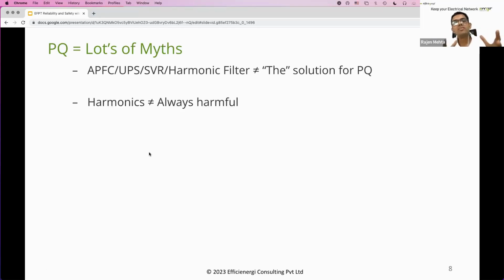The next myth is that harmonics are always harmful. I used to sell harmonic filters for a living in my earlier innings. I would jokingly say I got booted out from that venture because I was never a good marketer or salesman, since 6 out of 10 of my customers, we used to tell please do not do anything to your harmonics, please do not buy a harmonic filter, because that's not the problem you are running after. You're chasing the wrong cat. You need to focus on something else, which is the problem with respect to equipment malfunction, overheating, downtime, and so on. So remember, harmonics are not always harmful.